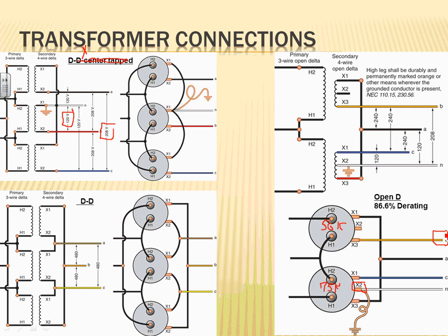Any comments, guys, about this system? Where do you get this system? 240, 120, three-phase. So that's called open delta. Open delta means two transformers. If you put three transformers in your center tap, that will be your center tapped closed delta. Center tap closed delta instead of open delta. Not common, but be aware. Mistake number one, and you can see the voltages here.